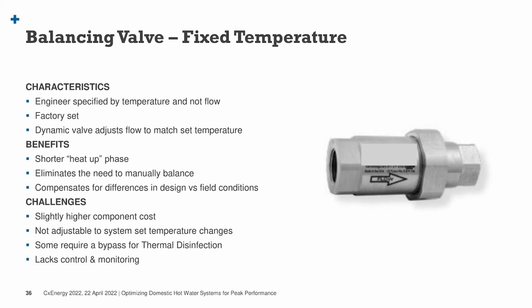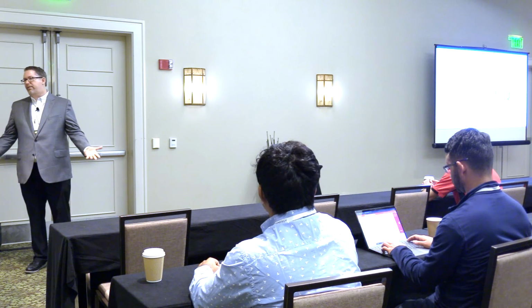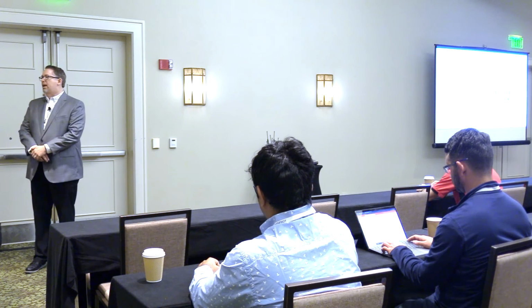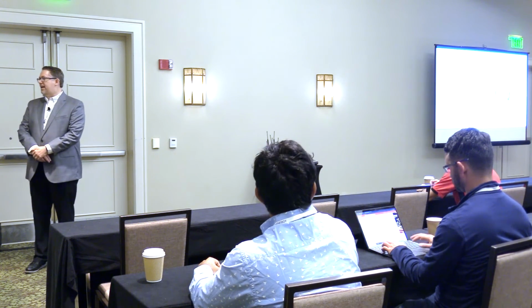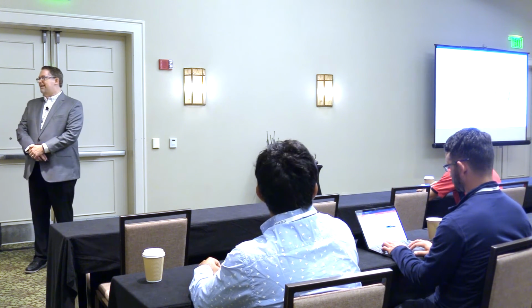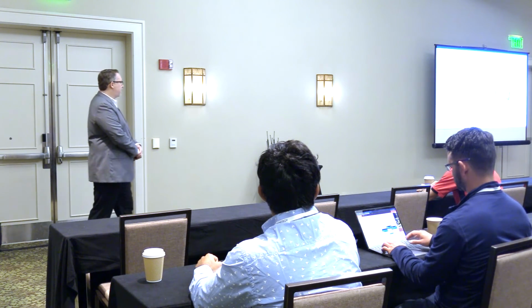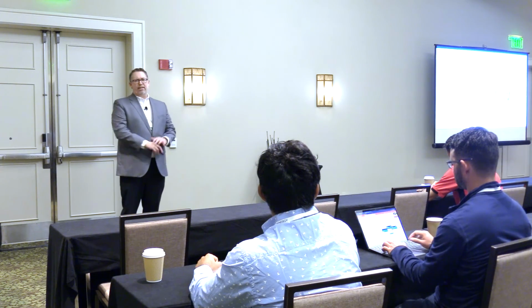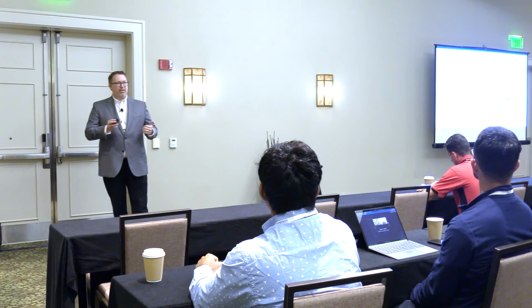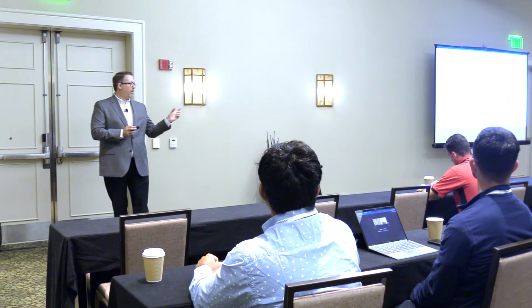So, fixed temperature. These actually have a wax element inside of them. They're going to dynamically adjust. This particular type is a fixed temperature, so again the engineer specifies they want a 120 degree return temperature or a 115 degree return temperature. This is factory calibrated to that temperature. It gets installed and then they dynamically adjust throughout the day. So some may call them automatic balancing valves, and there is a difference between automatic and automated. We'll talk about it, but this here is basically the wax element either expanding or contracting, trying to hit that target temperature.